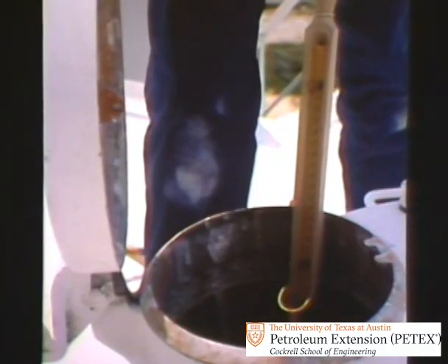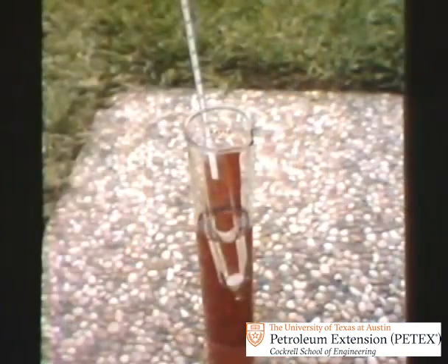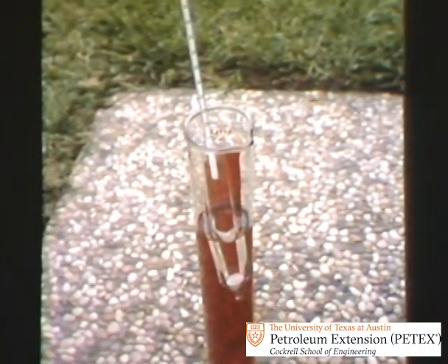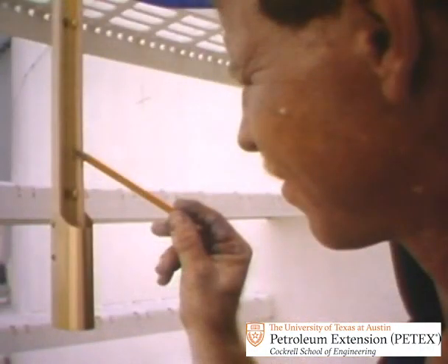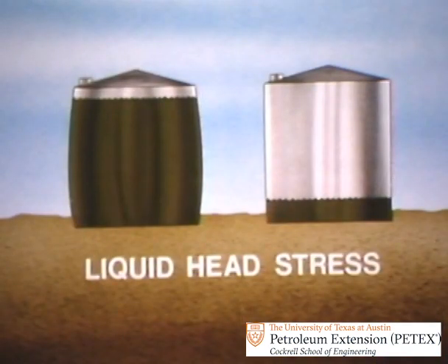In tanks of over 500 barrels capacity, the temperature of the tank's contents must be taken, as well as the gravity of the contents and the outside temperature of the tank shell. These measurements allow calculations to be made to compensate for liquid head stress, the tendency of a large tank to expand and contract as liquid is moved in and out of it.